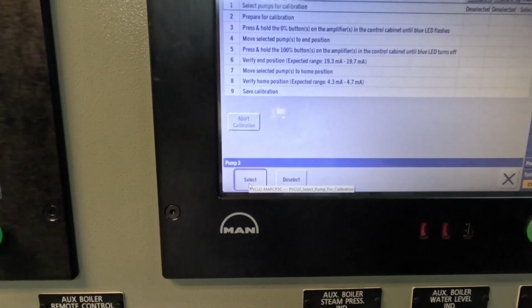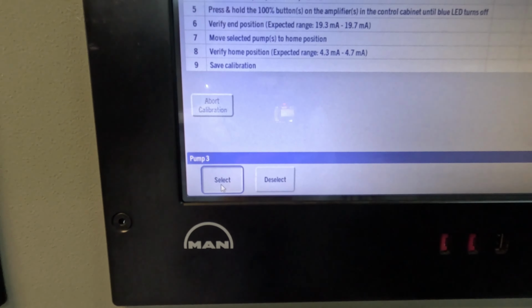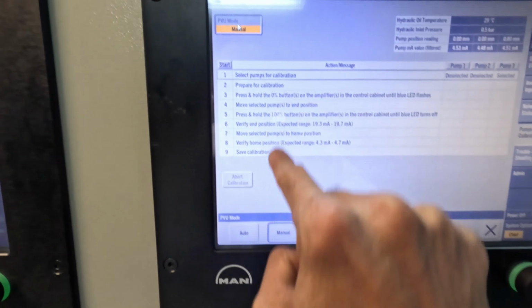I have a cargo engineer standing by in the switchboard room. We have changed the position transmitter, and because of that, remember, the hydraulic circuit was open, so we have one engineer standing by to monitor if any hydraulic leaks pop up. For this first step of the calibration, I click on auto, change this to manual, and select pump number 3. So we are ready for calibration. The first step of calibration is to change the PVU to manual mode, which I just did. Pump 3 has been selected.